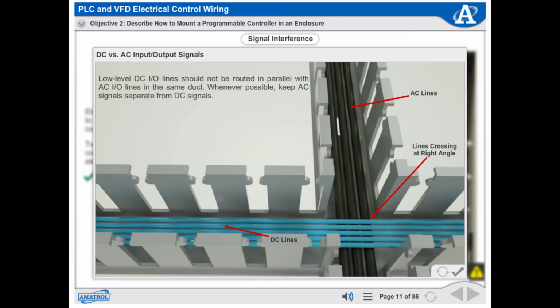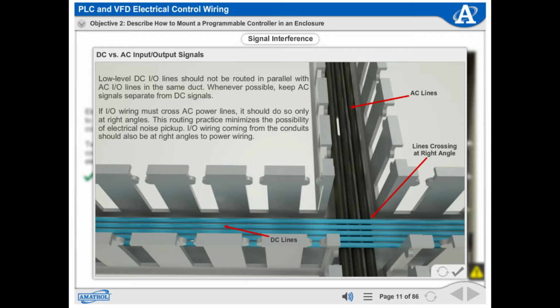Low-level DC I/O lines should not be routed in parallel with AC I/O lines in the same duct. Whenever possible, keep AC signals separate from DC signals. If I/O wiring must cross AC power lines, it should do so only at right angles. This routing practice minimizes the possibility of electrical noise pickup. I/O wiring coming from the conduits should also be at right angles to power wiring.